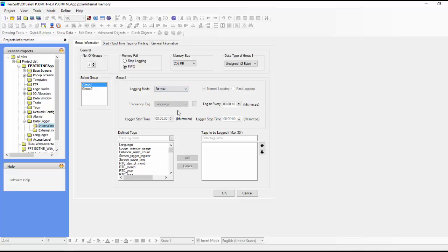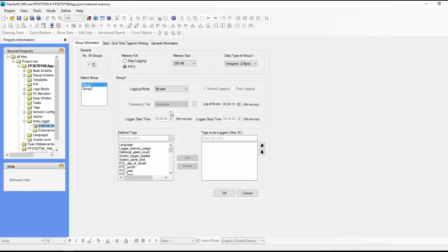We have a bit task. So there's a bit that's basically create a log, and whenever that is turned on through logic or wherever, it will create a log. And this is also log at every 10 seconds or you can say whatever this is. So in other words, if the bit is on and it's continuously on, then it will create a log every 10 seconds or whatever you set this time interval to.